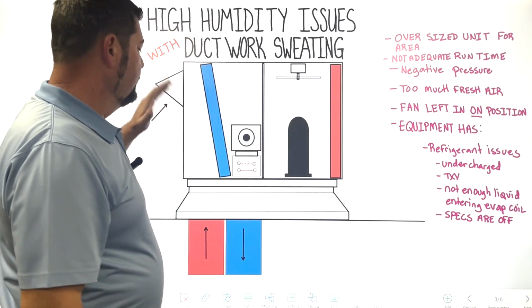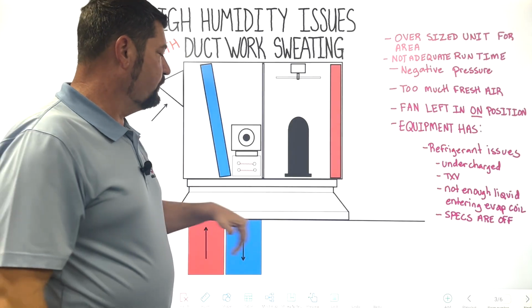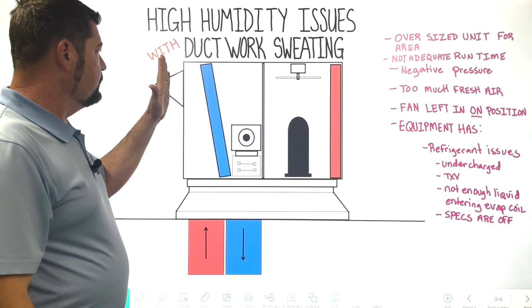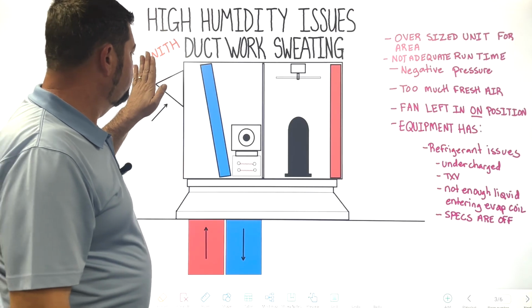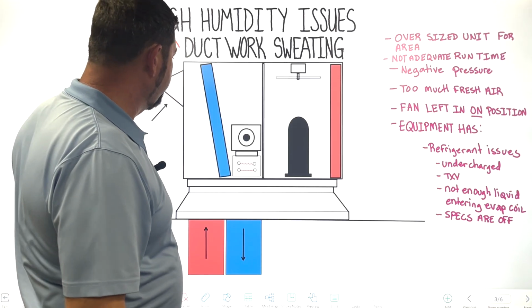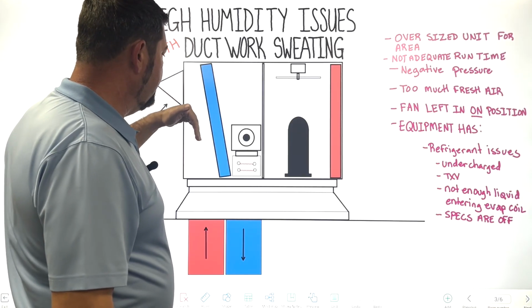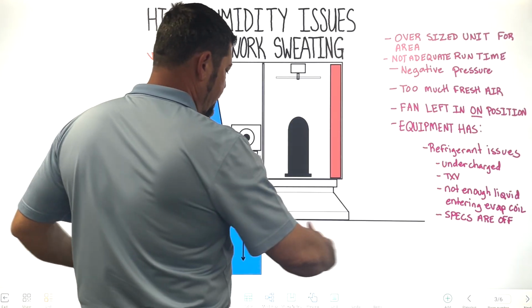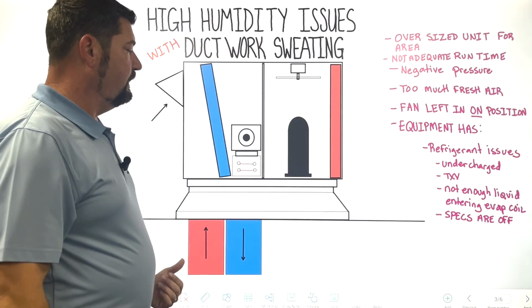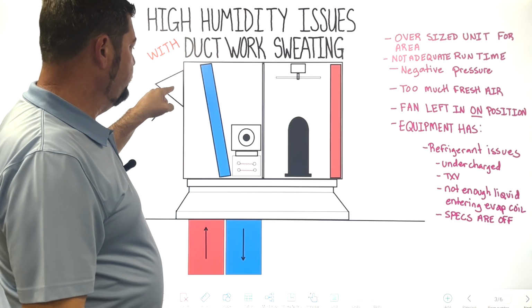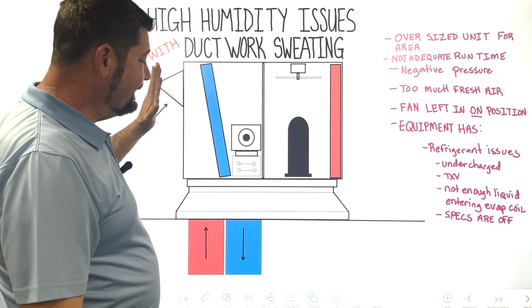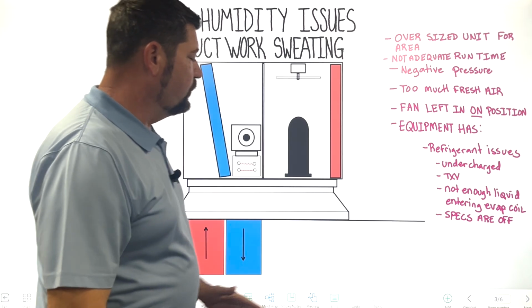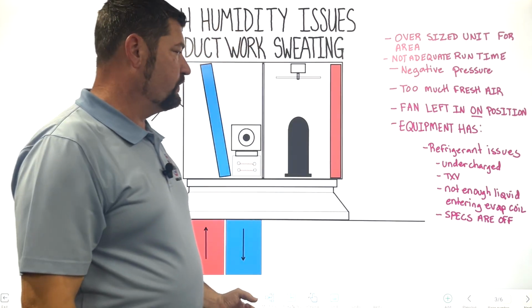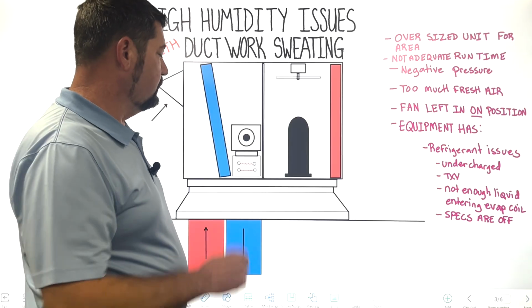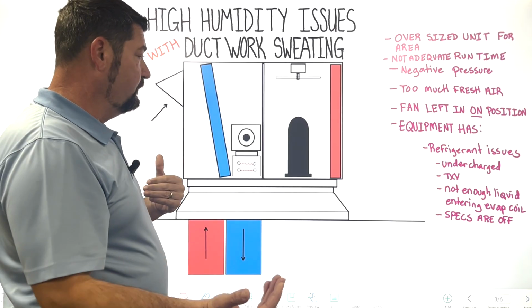Let's just say that you have negative pressure on the building and there is no positive fresh air damper to bring any air in to stop that negative pressure. Then the same thing with the fan in the on position, even without the needed fresh air, you're still bringing in negative pressure into the structure. So it's like a double-edged sword.